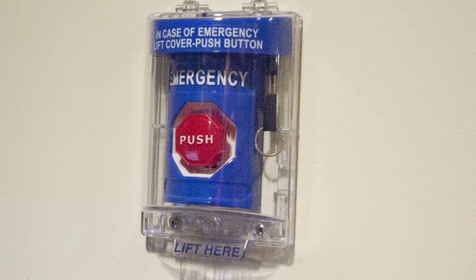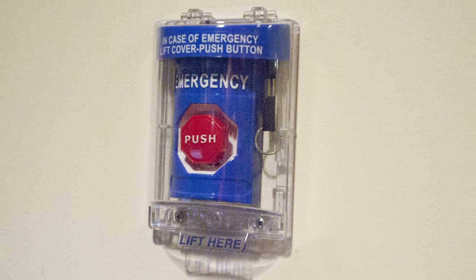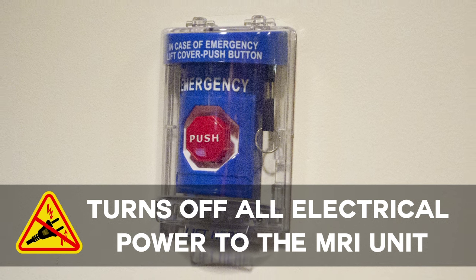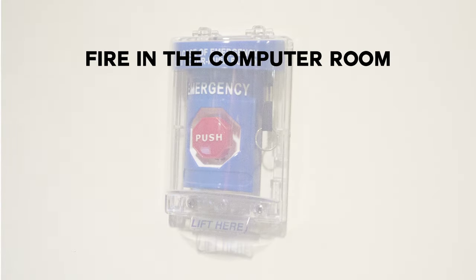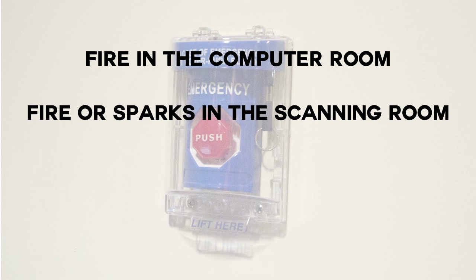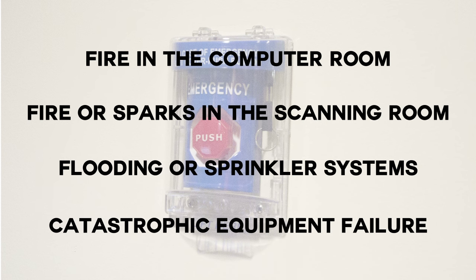In the case of an emergency, there are two buttons to be aware of right outside the MRI exam room, near the technologist console area. One is an emergency power off button. This turns off all incoming electrical power to the magnet's power distribution unit, or PDU. Shutting down power may be required in emergency situations such as fire in the computer room, fire or sparks coming from the scanning room, flooding or sprinkler systems going off, or catastrophic equipment failure.